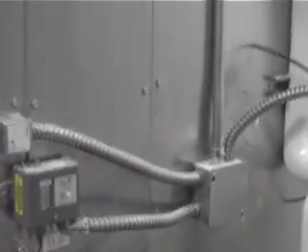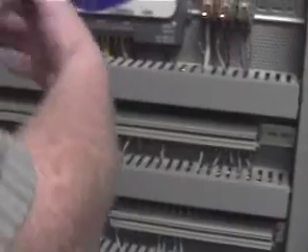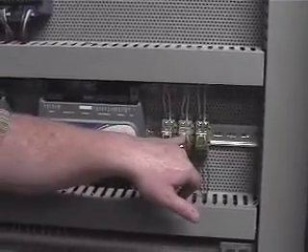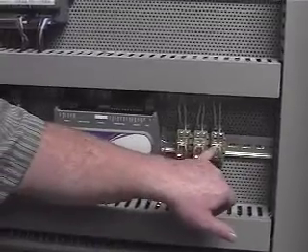Freezestats. Right here you've got 4 of them, as well as you're averaging. They're all set, I believe, at 37 or 35, right around there. Are they hardwired or software? Hardwired. And that's a good point. I'll put the drawing on this one as well. One of them is your high duct static. The other one is your low temperature alarm. This one right here will be the low duct static.